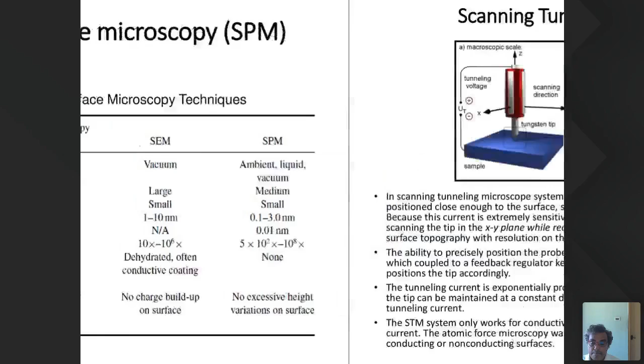Let us see how the scanning tunneling microscope works. You can see the picture here. It is an enlarged picture of this tungsten tip when it is close to the sample. There is a scanner that gets feedback from the sample. In a scanning tunneling microscope system, a bias voltage is applied to the sample, and the tip is positioned close enough to the surface so that a tunneling current develops through the gap. That means the tunneling current develops between the very sharp tip and the sample. It is not going to touch exactly; there is some gap. Because this current is extremely sensitive to the distance between the tip and the surface, scanning the tip in the XY plane while recording the tunneling current permits mapping of the surface topography to atomic scale resolution.